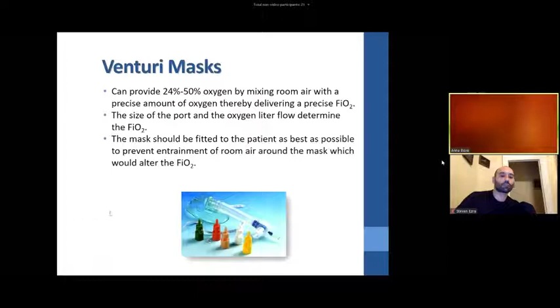But let's say 6 liters is going to give you 24%. But it'll tell you on the bottom. You see where the port is? Right here on that round section, it'll say how many liter flows, and you'll just turn the liter flow up to what it says. So if it says 6 liters, you turn it up to 6 liters, and it'll give you that percentage. And you need humidification.